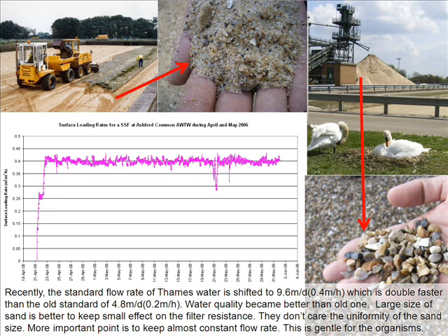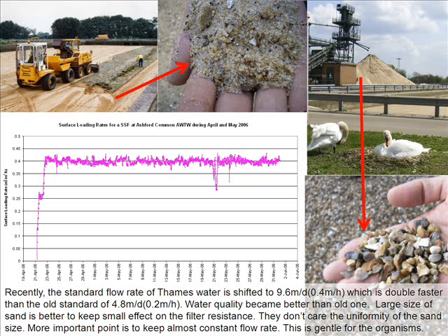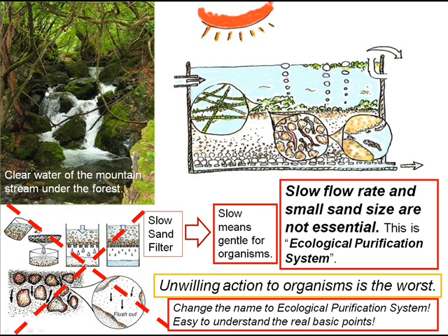Recently, the standard flow rate of Thames Water in London has been shifted to 9.6 m per day, which is double the old standard of 4.8 m per day. Water quality became better than the old one. Large size of sand is better to keep the filter resistance small. They do not care about the uniformity of sand size. The more important point is to keep an almost constant flow rate — this is gentle for the organisms. Slow sand filter is not a mechanical sieving by fine sand and slow flow rate. Slow means gentle for organisms. Slow flow rate and small size of sand are not essential. This is an ecological purification system.